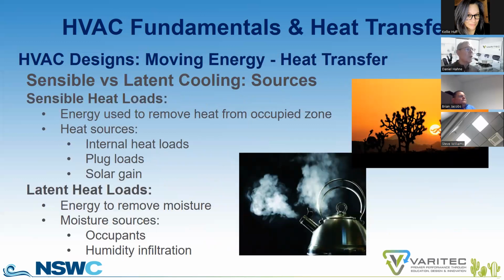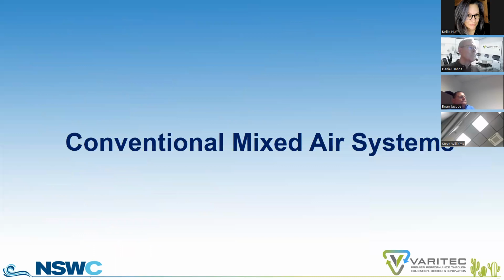So what are the sensible heat loads in a building? Occupants, internal heat loads, plug loads, solar gain on perimeter walls, anything that causes an increase in a thermostat. What adds latent energy to a building? What adds moisture? Occupants, humidity infiltration through perimeter walls, kitchens, sinks, restrooms, etc. Open drain pans and ceilings add to the humidity of a building. So let's look at a conventional mixed air system and how it handles the total load of a building and how it operates so that we can control a building's environmental condition.